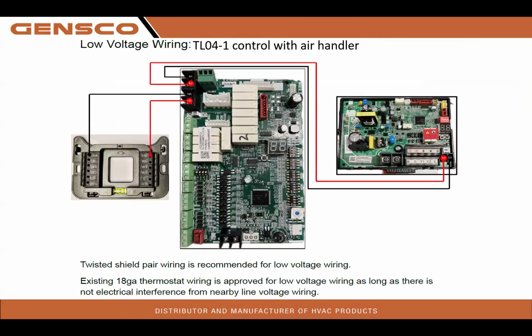Let's talk about our 2 wires. Fully communicating. Here we have our TL04 stat. Notice I was telling you that we can wire this TL04 stat conventional, 24-volt, or fully communicating. In this description you see here is just a standard 2-wire design. HA and HB go to HA-HB on the indoor board. And then S1, S2 travels from the indoor board all the way out to the outdoor board and lands on S1, S2. So let's review that real quick. 2 wires, HA-HB to the indoor board, HA-HB, S1, S2, out to S1, S2, out at the outdoor board.